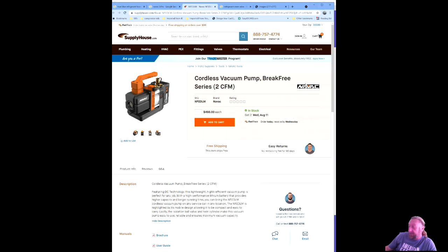Yeah, but what happened was one of my guys changed a compressor on an LG, and then he went back and the compressor failed or the system failed. The point being is that they're saying if you didn't get a 500 micron, that's why your system failed. I don't think you have to get a 500 micron vacuum in order to have a perfect system. You can get a 700, you'd be good.